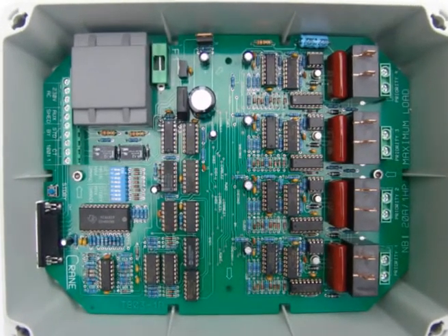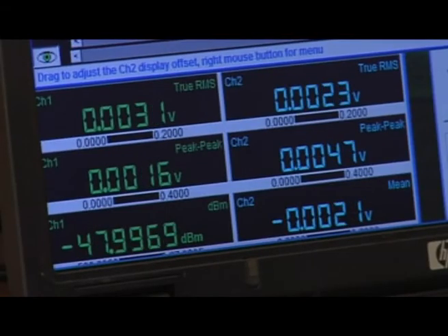The important thing to know is that Power Guard is self-regulatory — it doesn't need external signals to make it work. The switching elements have been tested to an equivalent of 50 years of switching duty cycles at higher currents than what we actually advocate. You can set the demand criteria for each household, and the moment you transgress that, Power Guard will shed devices like geysers, swimming pool pumps, underfloor heaters, and air conditioners to maintain a low peak demand.